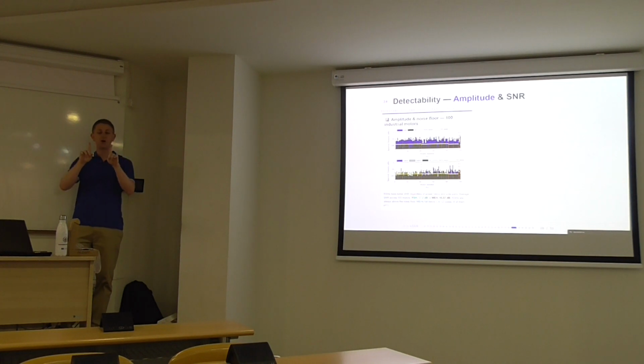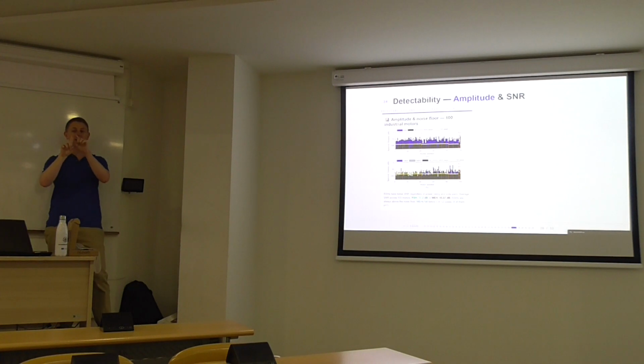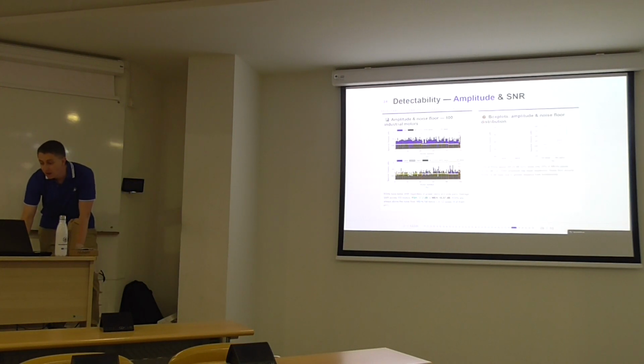What we have done is, first of all, we look at which is the highest amplitude harmonic, the lower or the upper. Then, with the upper one, I see what the noise floor is around it. So the same with the rotor load harmonic: we record amplitude and noise floor. And here are just the box plots that exploit the statistical information in this graph.